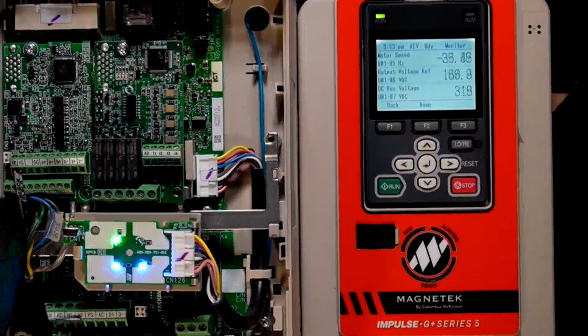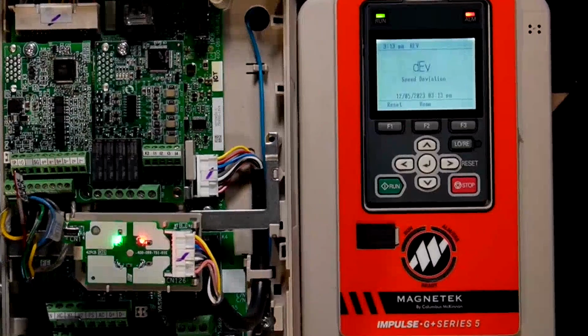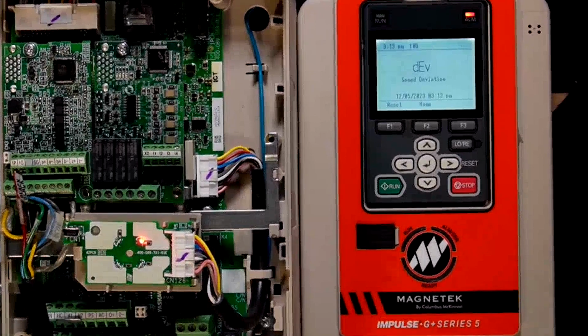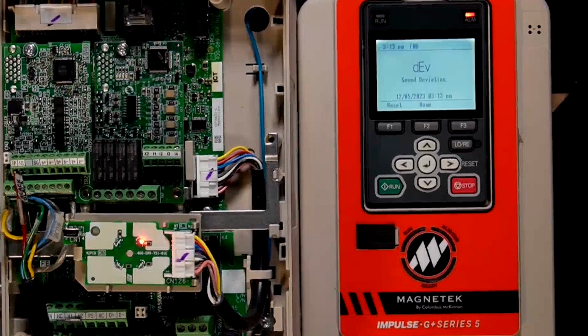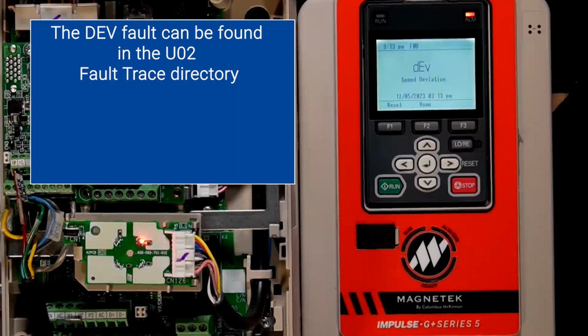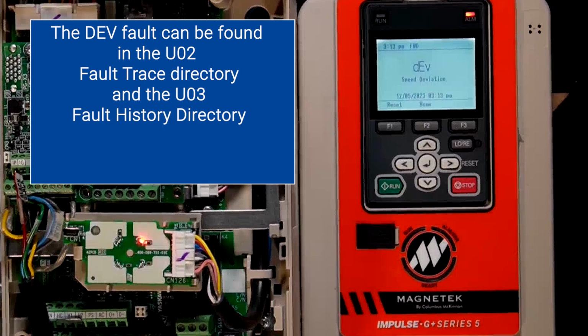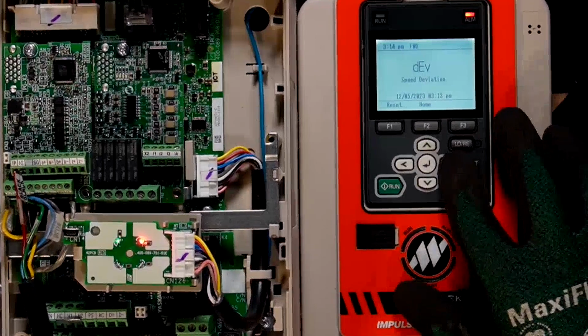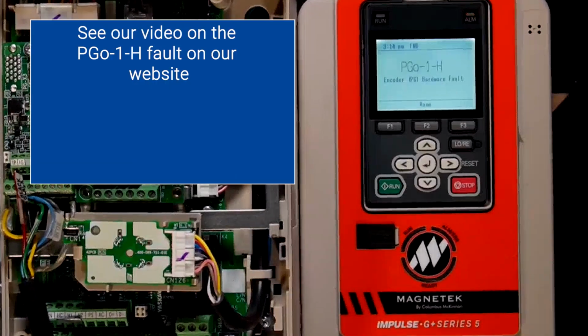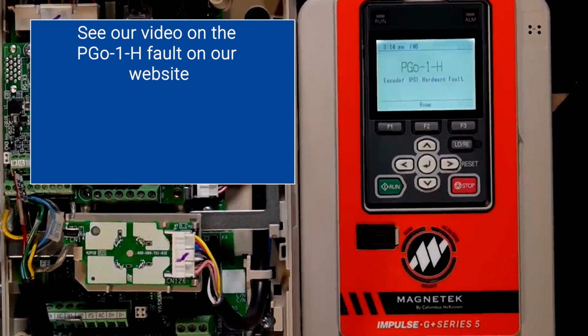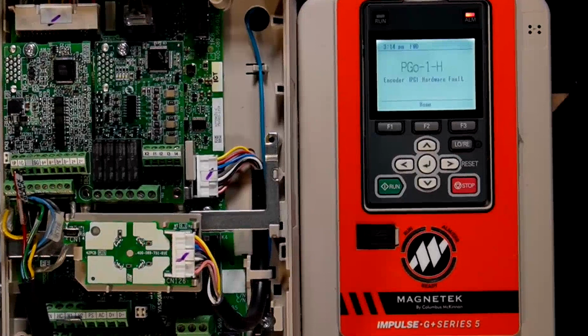So I'm going to give the drive a run command. I'm going to pull this wire off, and there is a DEV fault. Now this DEV fault will be found in the fault trace, the U2s, as well as the fault history, the U3s. I will now reset the fault, and now the drive is locked into a PGO-1-H, indicating that the drive now has not seen encoder signal as it should.